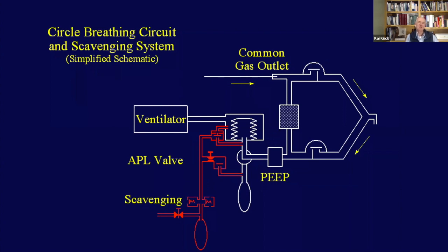There is a way of turning this into a non-circulatory circuit, if you will, and that is by having a very large fresh gas flow. The manufacturers have all provided guidance documents, and I've seen them. They all come with a big disclaimer: this is off-label use. We don't recommend that, but if you want to use it, this is what you need to pay attention to. They suggest that this fresh gas flow should be about 1.5 times your minute ventilation. And remember, minute ventilation is tidal volume times respiratory rate.